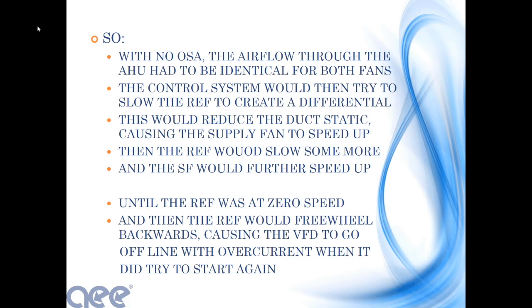And it wasn't a problem until the fan tried to start again, the return fan. The VFD, trying to overcome this inertia going the wrong way, took itself offline, and the control guy decided that the electrical design was bad, that the VFD was faulty. He didn't understand the physics of the air handling system, and no matter how much you tried to slow down that return fan, the air going through both machines was going to be exactly the same. It couldn't be anything else. That was really fundamental. He should have understood that.